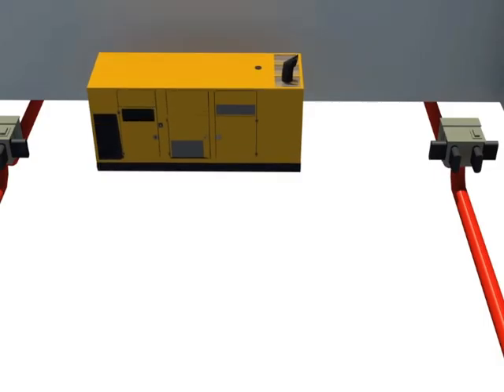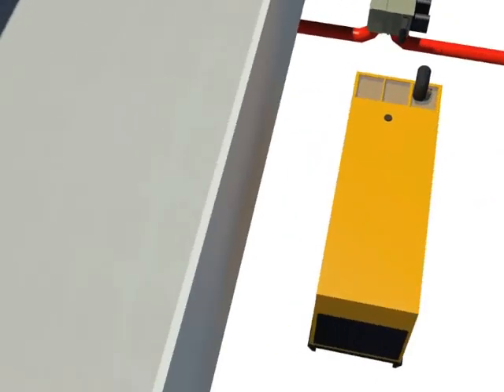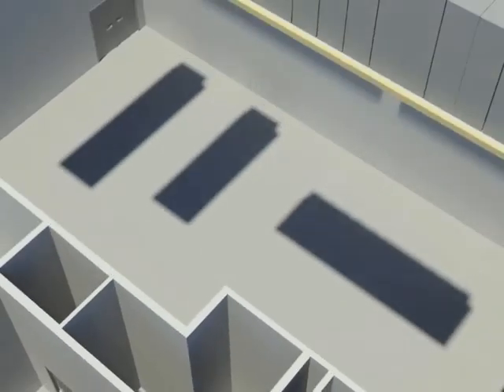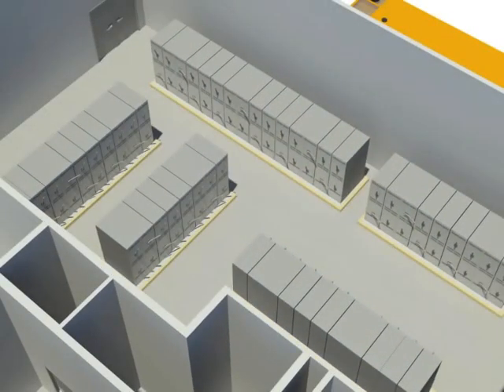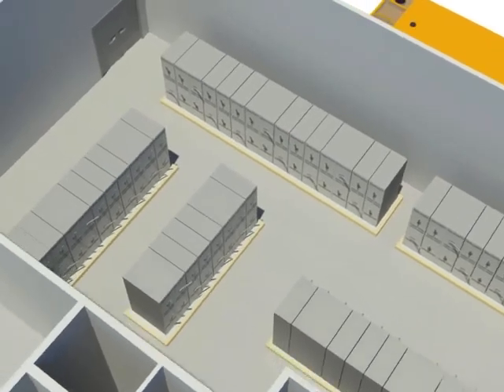In the unlikely circumstance that commercial power from both feeds to the site are temporarily disabled, these systems are supplemented by a 1,000 kVA diesel generator and 1,000 gallons of diesel fuel on site, which can power the center for as long as needed. All power sources transfer through redundant electrical switchgear, a system that manages a smooth transition of power between supplies as needed.